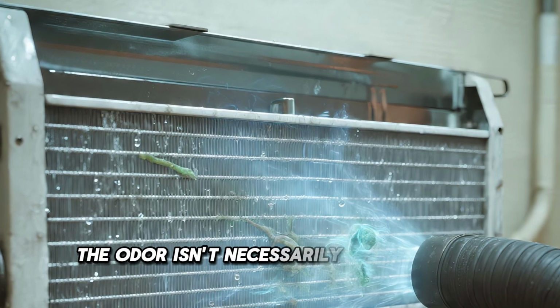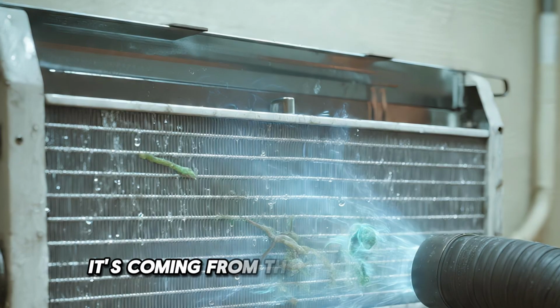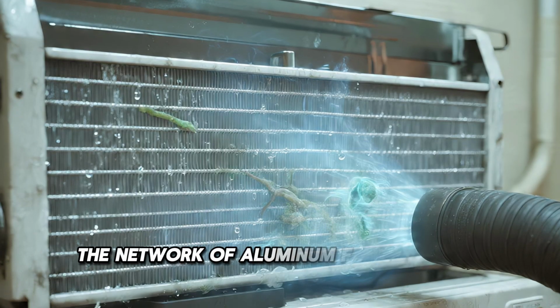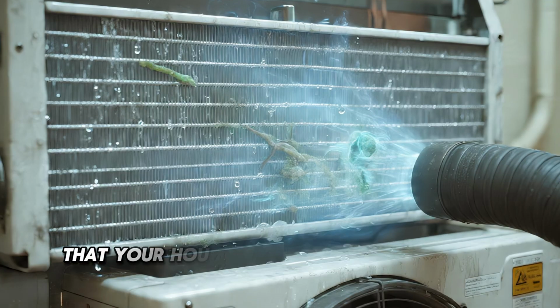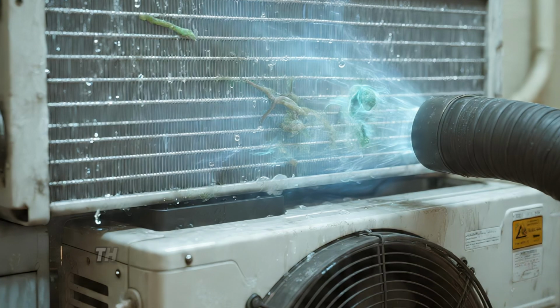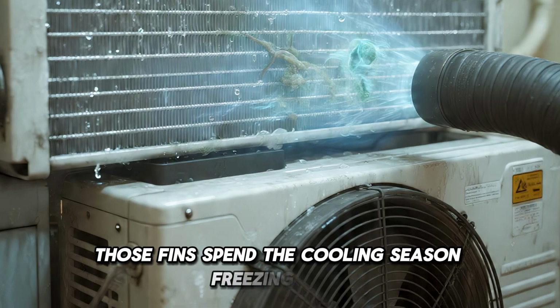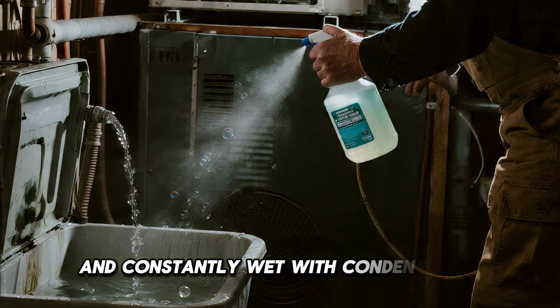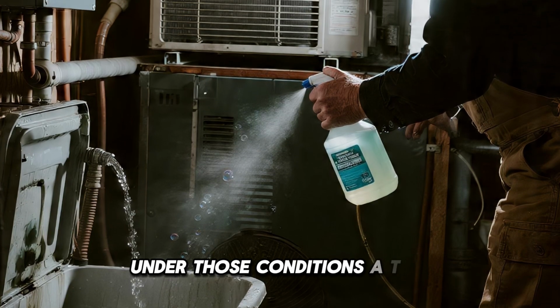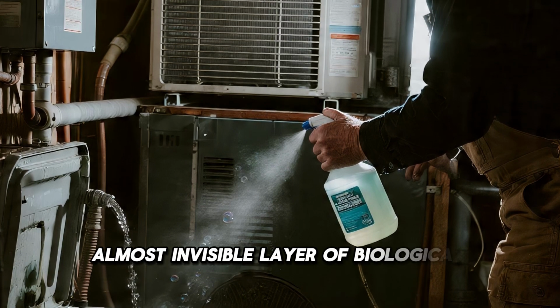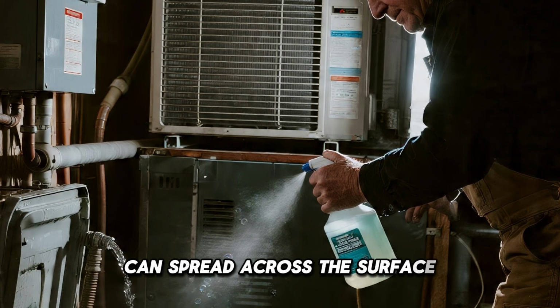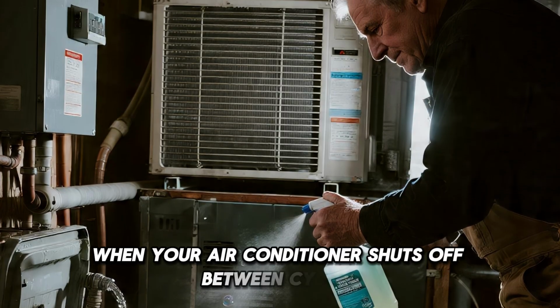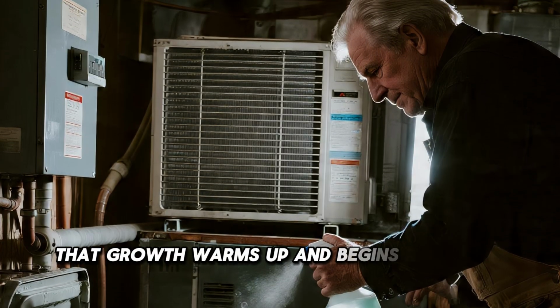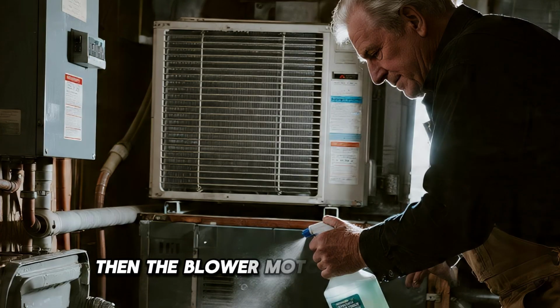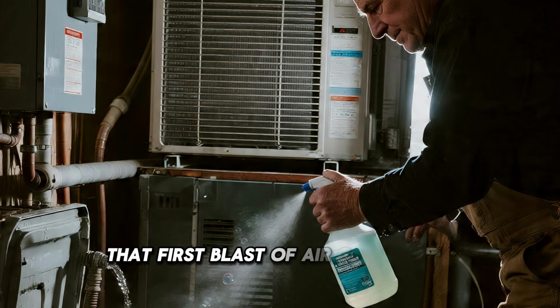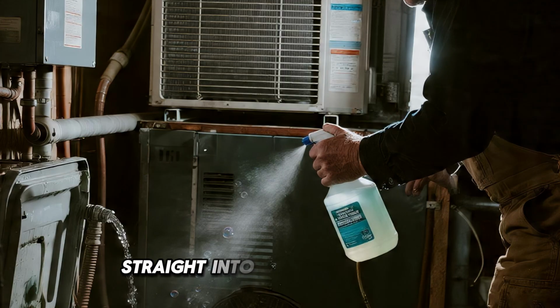The odor isn't necessarily coming from your ducts. It's coming from the evaporator coil, the network of aluminum fins inside the indoor unit that your household air passes across to become cold. Those fins spend the cooling season freezing cold and constantly wet with condensation. Under those conditions, a thin, almost invisible layer of biological growth can spread across the surface. When your air conditioner shuts off between cycles, that growth warms up and begins releasing odor. Then the blower motor starts again. That first blast of air carries the concentrated smell straight into your living space.